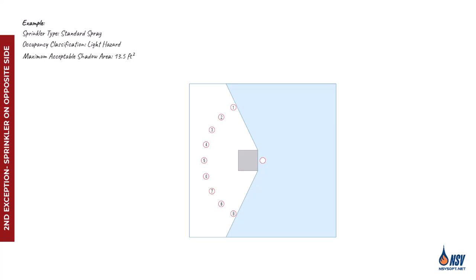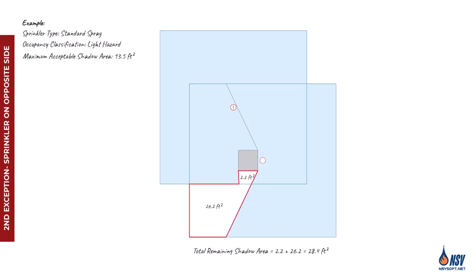To evaluate which of the sprinklers, numbered 1 through 8, can be considered as being on the opposite side that minimizes the shadow area, we begin our assessment with sprinkler 1. When we draw the coverage area of sprinkler number 1, we can see that although it covers part of the shadow area created by the first sprinkler, the remaining shadow still exceeds the acceptable limit. Therefore, sprinkler 1 cannot be considered the opposite side sprinkler, as it does not sufficiently minimize the shadow area caused by the obstruction.